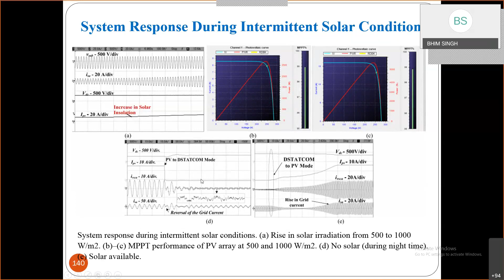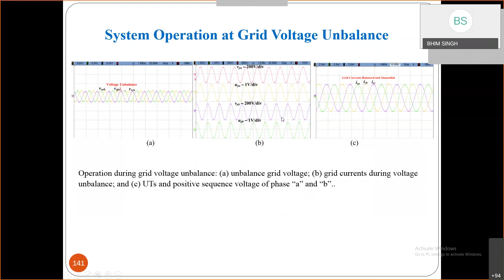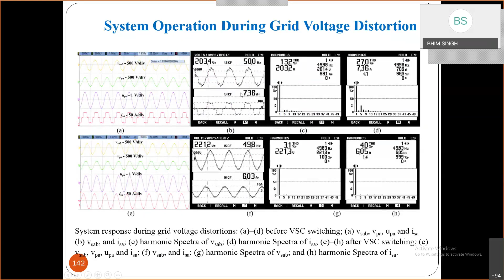You can see how the inverter current changes, typically to compensate the local load. Even if your voltages are unbalanced, we are able to modify the control so that the system works very well. So not only do we have to use one control, but we have to use many control algorithms, even for filtering the voltage. From unbalanced and distorted voltage also, the system works very well. You can see how much the distortion is, with 13.2% THD in the voltage, but the current THD we are still able to get around 4% without much problem.